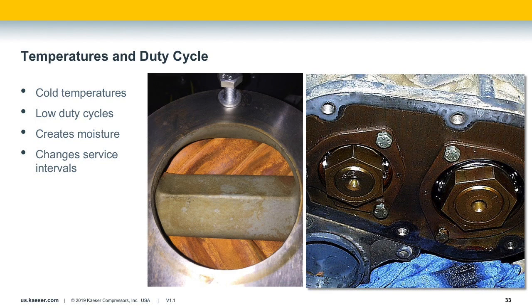If the minimum pressure check valve is stuck open or has a leak and water starts to backfill, it will fill up the unit with water and eventually displace the oil, which can cause catastrophic failure. This unit in particular lacked proper filtration maintenance, and eventually the 400-gallon receiver tank filled up with water and a minimum pressure check valve was stuck open due to lack of maintenance and filled the compressor up with water. This resulted in replacement of an air end.